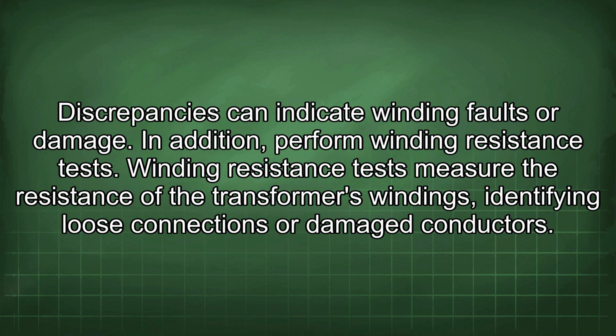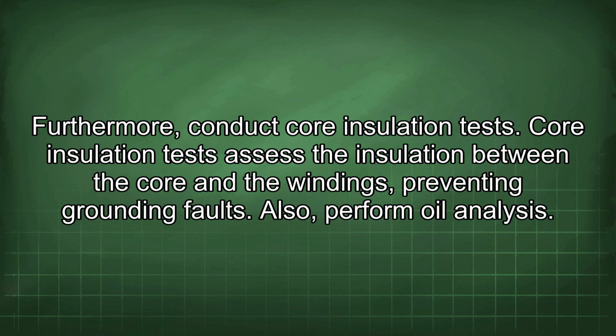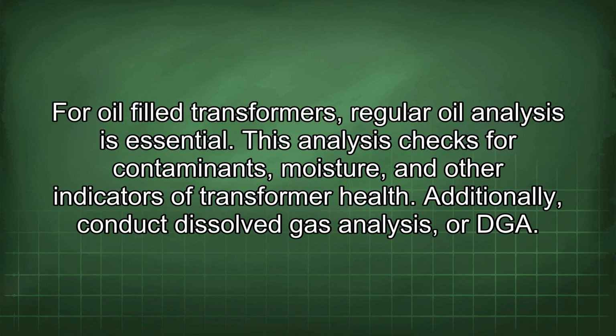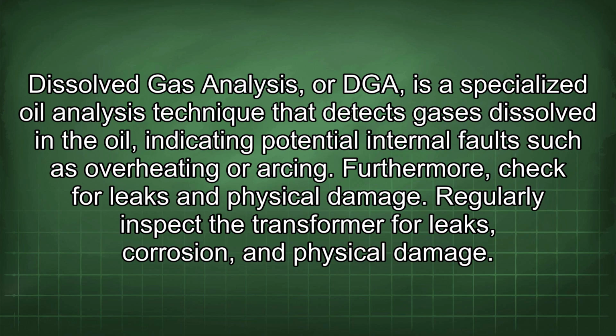In addition, perform winding resistance tests. Winding resistance tests measure the resistance of the transformer's windings, identifying loose connections or damaged conductors. Furthermore, conduct core insulation tests. Core insulation tests assess the insulation between the core and the windings, preventing grounding faults. Also, perform oil analysis. For oil-filled transformers, regular oil analysis is essential. This analysis checks for contaminants, moisture, and other indicators of transformer health. Additionally, conduct dissolved gas analysis, or DGA. Dissolved gas analysis, or DGA, is a specialized oil analysis technique that detects gases dissolved in the oil, indicating potential internal faults such as overheating or arcing.